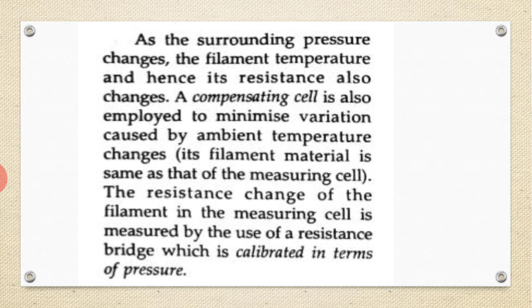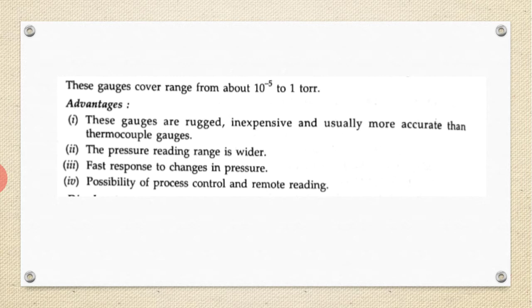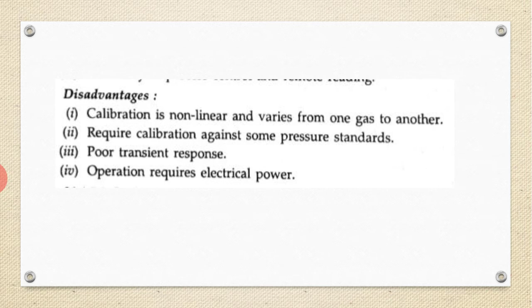These are the advantages: inexpensive and rugged, usually more accurate than thermocouple gauges, wider pressure reading range, fast response to change in pressure, and possibility of process control and remote reading. These are the advantages of the Pirani gauge. Some of the disadvantages: calibration is non-linear and varies from one gas to another, it requires calibration against some pressure standards, poor transient response, and operation requires electrical power. These are some disadvantages related to the Pirani gauge.